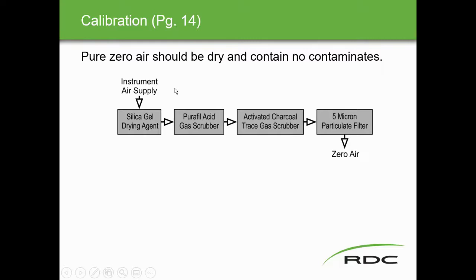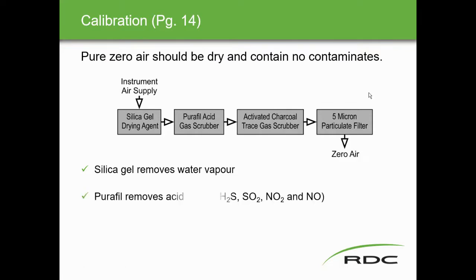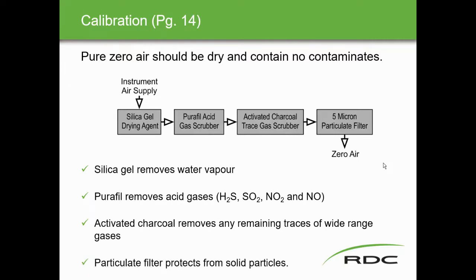For calibration, pure zero air must be dry and contain no contaminants. The zero air preparation system includes: silica gel (removes water vapor), Purafil acid gas scrubber (removes H2S, SO2, NO2, NO), activated charcoal trace gas scrubber (removes wide-range trace gases), and a 5-micron particulate filter. This level of purity is required because the chemiluminescence analyzer is measuring at parts per billion.